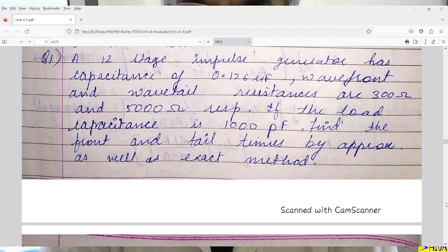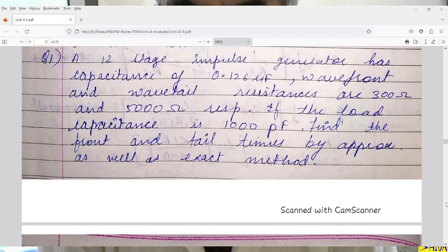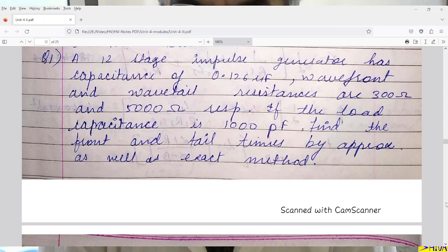All the equations of single stage impulse generator are valid for multistage impulse generator also. The only difference is that in case of multistage impulse generator, all the capacitors are discharged in series. So we have to take the equivalent circuit of N number of capacitors in series. Therefore, C1 will be equal to C divided by N, where N is the number of stages.